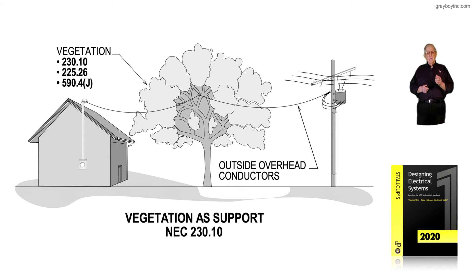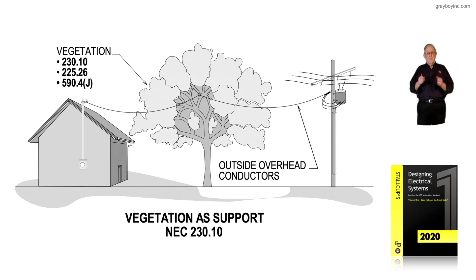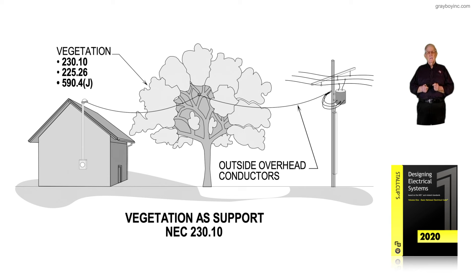They came back in and corrected that, changing it to just 'vegetation' as support. So anything where wind can blow the trees, the limbs and so forth, and stretch that wire, maybe pop it and break it — they said no, vegetation just can't be used at all. You need to set another utility pole and support those overhead conductors right.